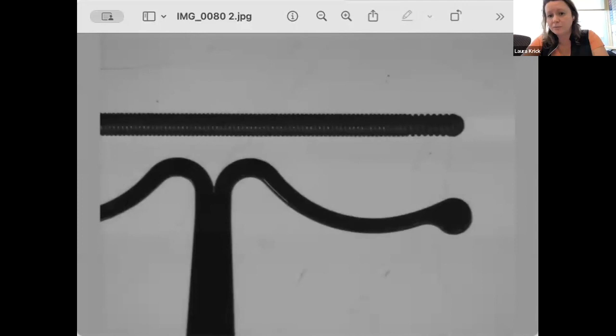And I know somebody said they saw a catheter break right at the edge of a SecurAcath, and that is not impossible if the catheter was pressed or kinked. The force there would probably have been more because of a kinking action, or the catheter might have been too tight under the dressing or turned at an angle. If that has happened recently and you have the device and the catheter, we would welcome it being returned so we can do a full investigation and assess that for you. But again, we have not had any proof or evidence that the device causes it, and we've tested it thoroughly with several brands of catheters to prove that it will not damage the catheter.